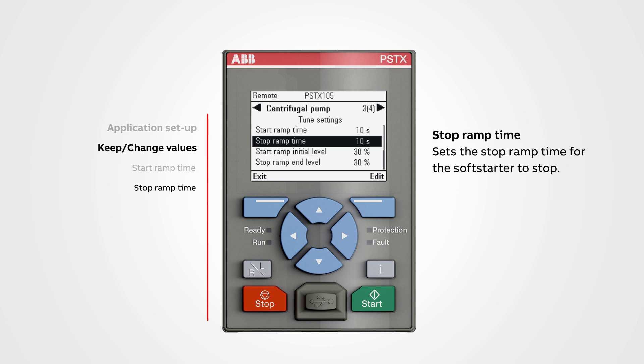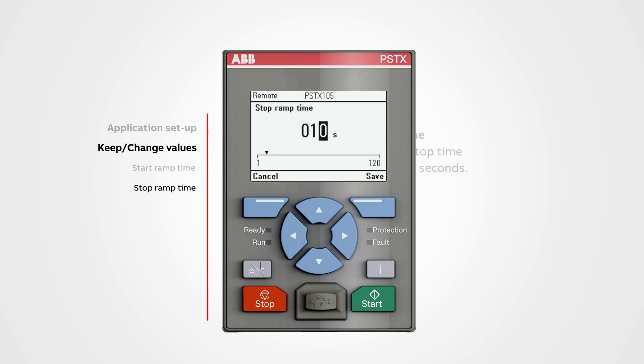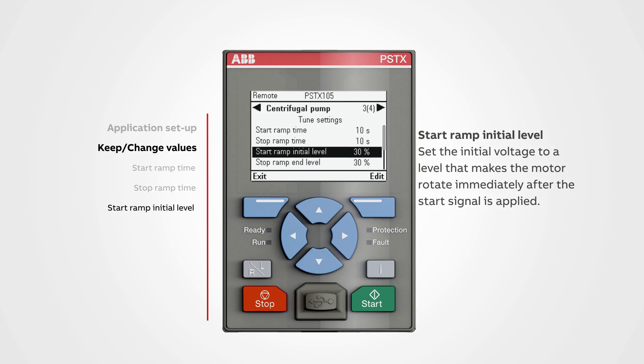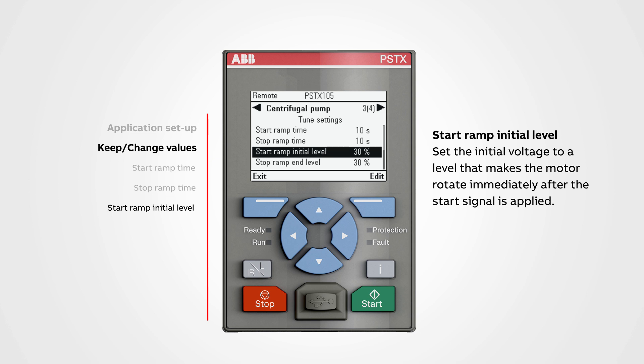Stop ramp time sets the time for the soft starter to stop. A low or high value will affect the stop time — with a higher value the stop time will be longer, and the opposite if you enter a low number. To change a value, push edit. We can set the stop ramp time between 1 to 120 seconds. Use the navigation buttons to change the value, then push save.